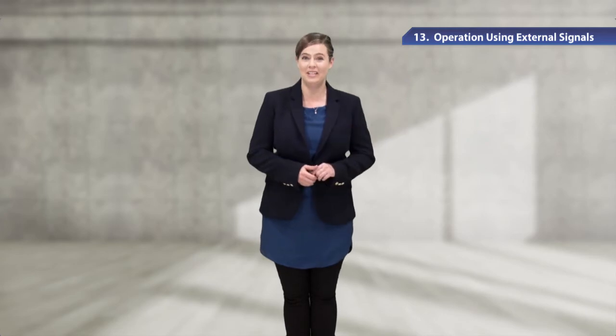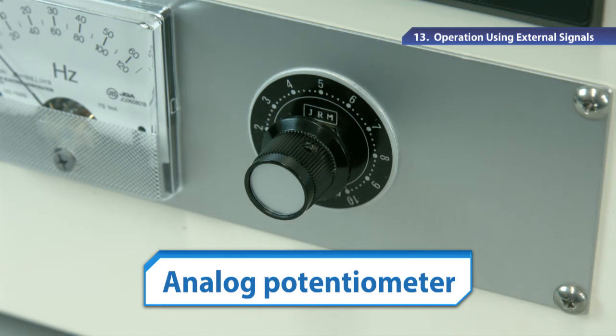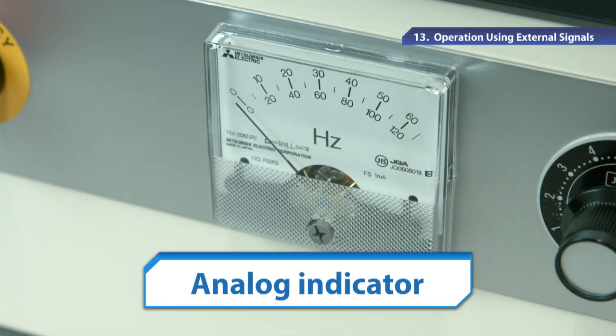The speed can be set to up to 15 levels with the preset switches for low, medium, and high speed. You can manually change the motor rotational speed by using an external potentiometer for analog signal. An analog indicator is also available for remote monitoring.